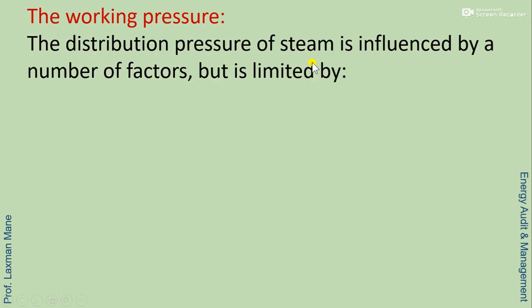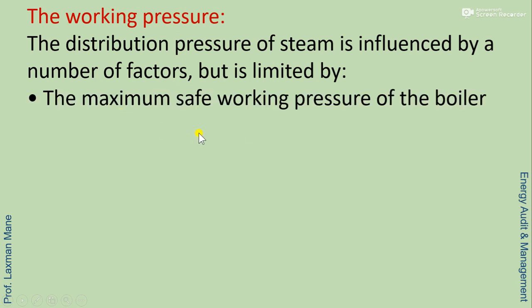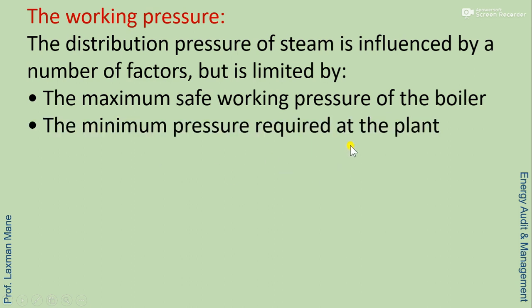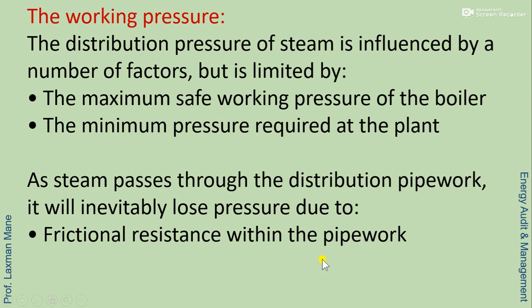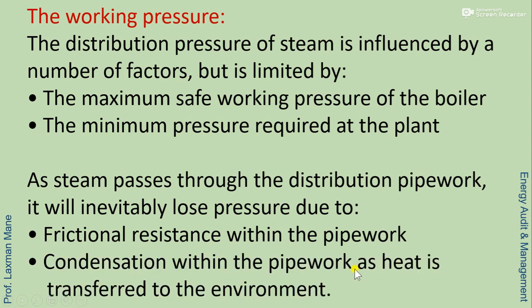The working pressure and distribution pressure of steam is influenced by a number of factors, but it is limited by the maximum safe working pressure of the boiler and the minimum pressure required at the plant. As steam passes through the distribution pipework, it will inevitably lose pressure due to friction resistance within the pipework and condensation within the pipework as heat is transferred to the environment.